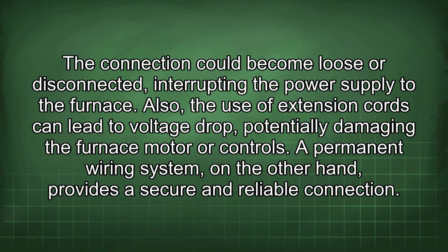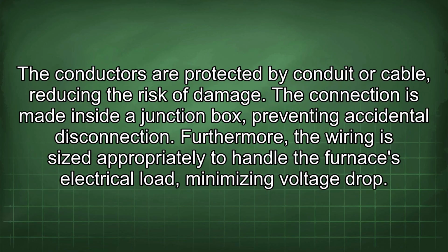A permanent wiring system, on the other hand, provides a secure and reliable connection. The conductors are protected by conduit or cable, reducing the risk of damage. The connection is made inside a junction box, preventing accidental disconnection. Furthermore, the wiring is sized appropriately to handle the furnace's electrical load, minimizing voltage drop.